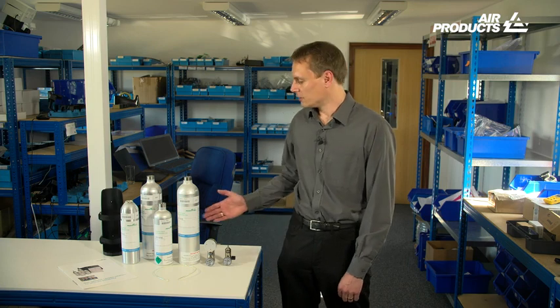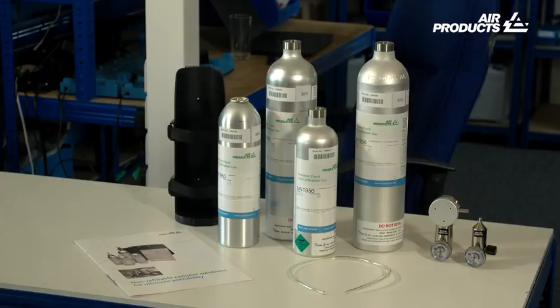The most common mode of supply of test gas is the non-refillable canister. The advantage is portability, enabling tests to be carried out in the field as well as in the workshop. They are easy to use because no tools are required to connect the gas control equipment, and generally there are no rental costs to consider, reducing the cost of having test gases on site. One common question is how many tests can be performed using each canister.